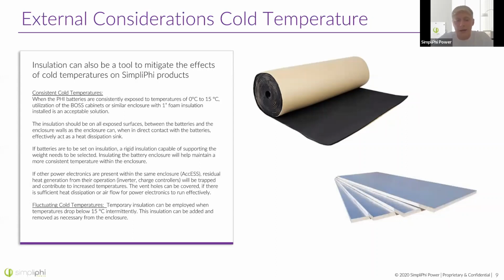One other thing to keep in mind: if you have additional electronics within the AccESS cabinet, such as inverters or charge controllers, these are going to generate some heat. Batteries on their own are very efficient, about 99% efficient each way, so you're only losing 1% of the energy going in and 1% coming out as heat. But other power electronics are much less efficient, losing anywhere from 5 to 10% often per device, which can generate quite a bit of heat. If you insulate the cabinet well, trapping that heat can really help keep the temperature up. This is the easiest way I find to mitigate cold temperatures in moderate environments, just insulating alone.